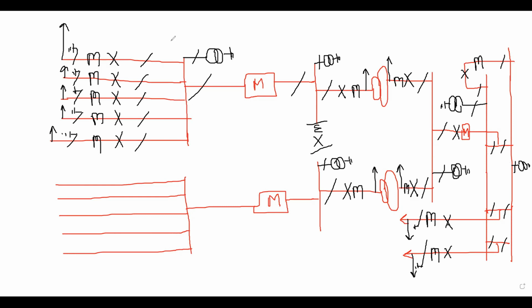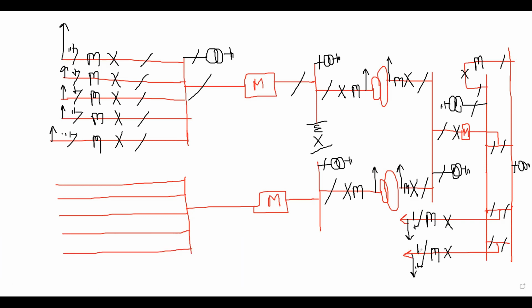Now, generally in the wind farms, in the wind generation, the synchronization will happen at 690 volts at the wind turbine. And if you see generating plants like hydro plants, this is connecting directly to the generator. This is directly connecting to the generator. So in those cases, you require potential transformers. In the renewable projects, you do not require the potential transformer at the 33 kV level. But we need a potential transformer on the 220 kV level only to know whether the voltage has come up in my substation during the commissioning stage. During the commissioning stage, just checking the voltage.